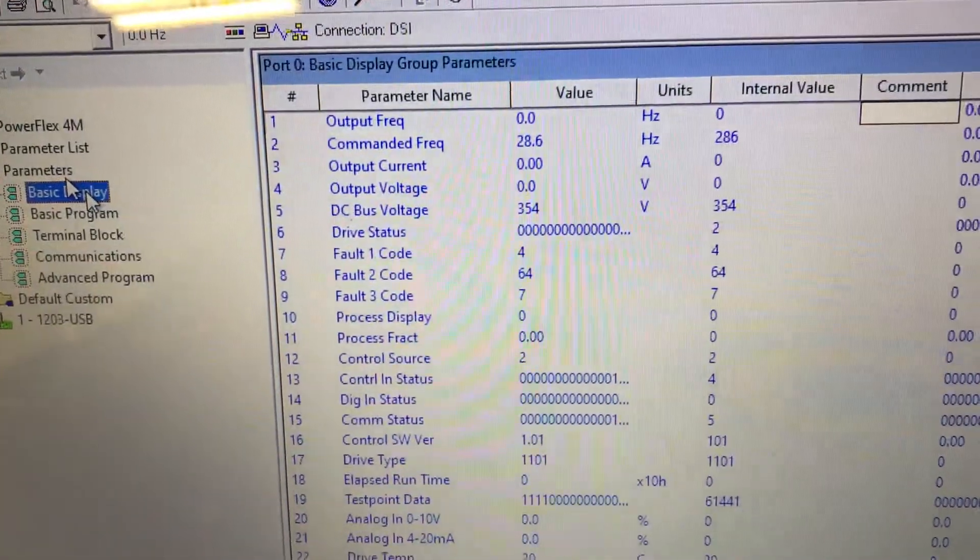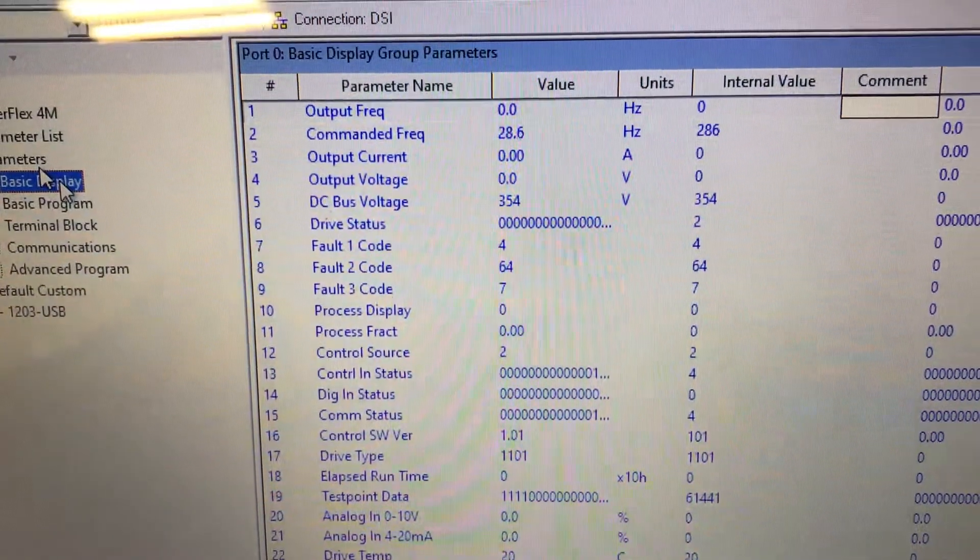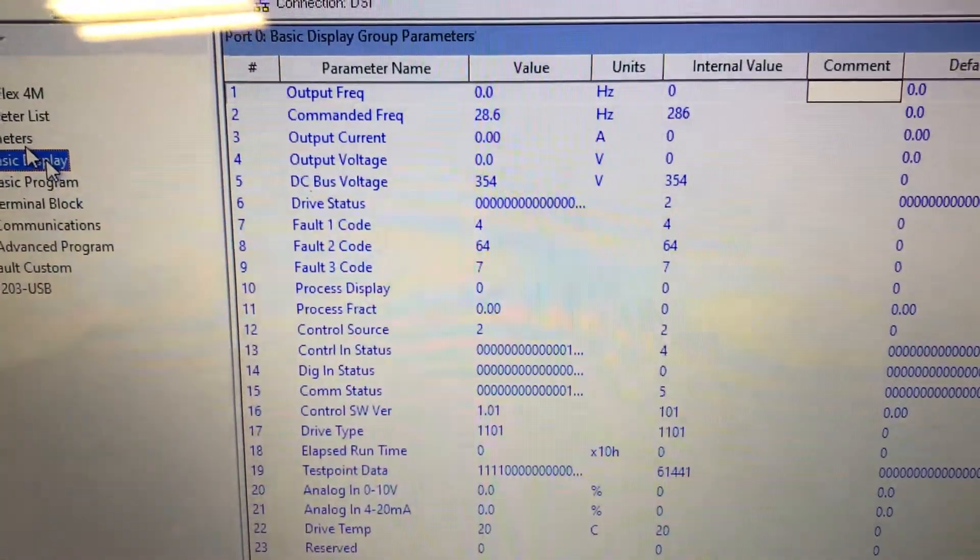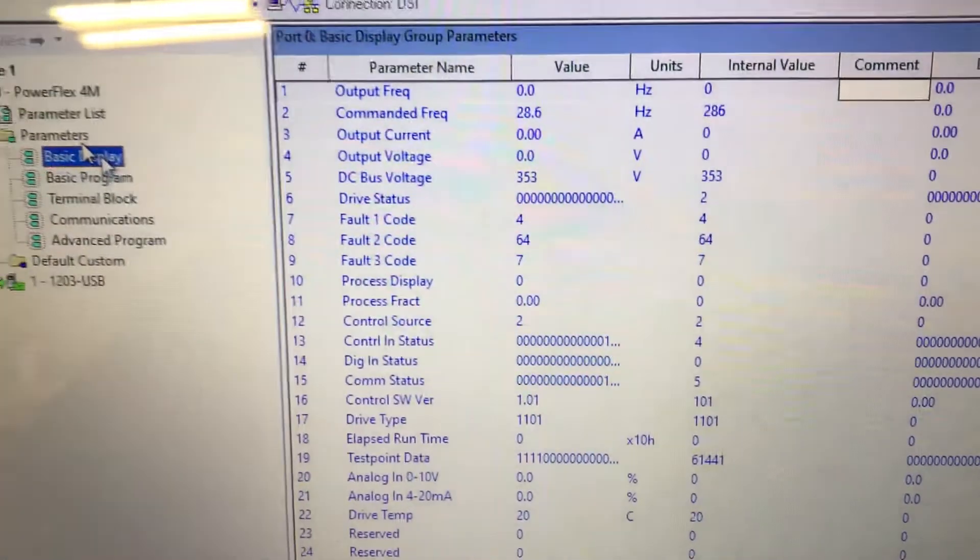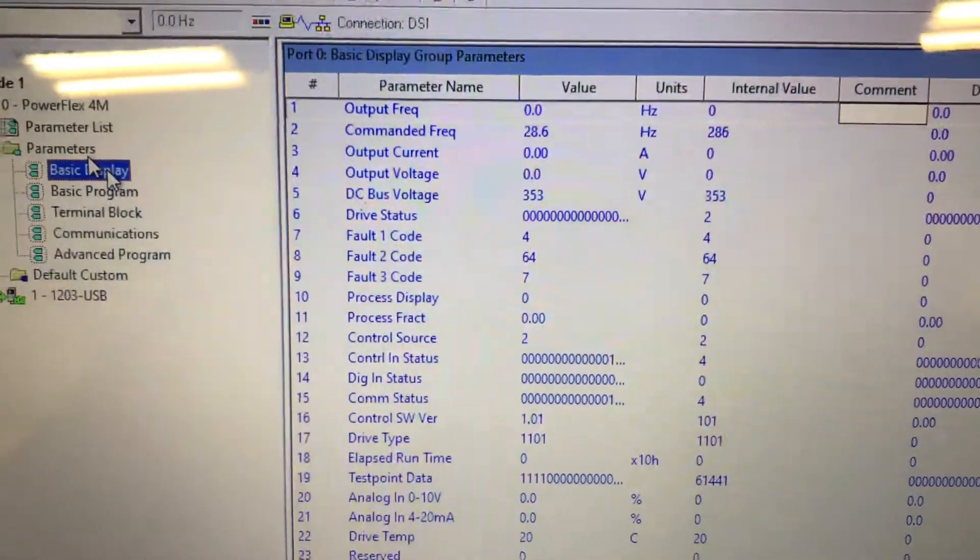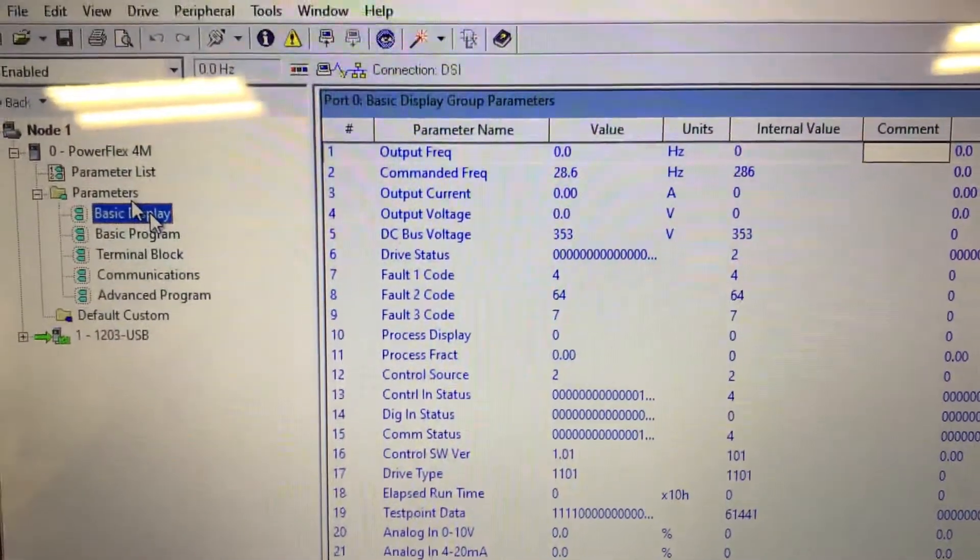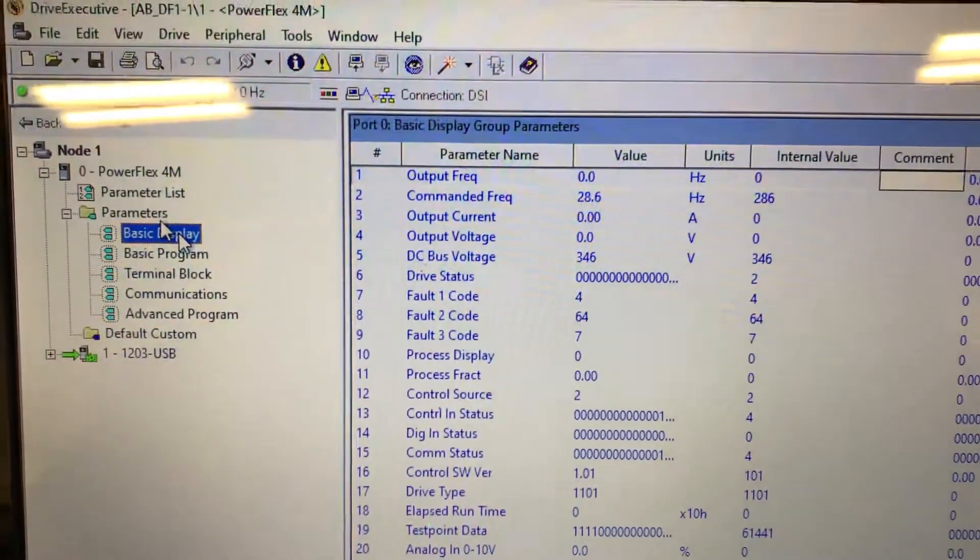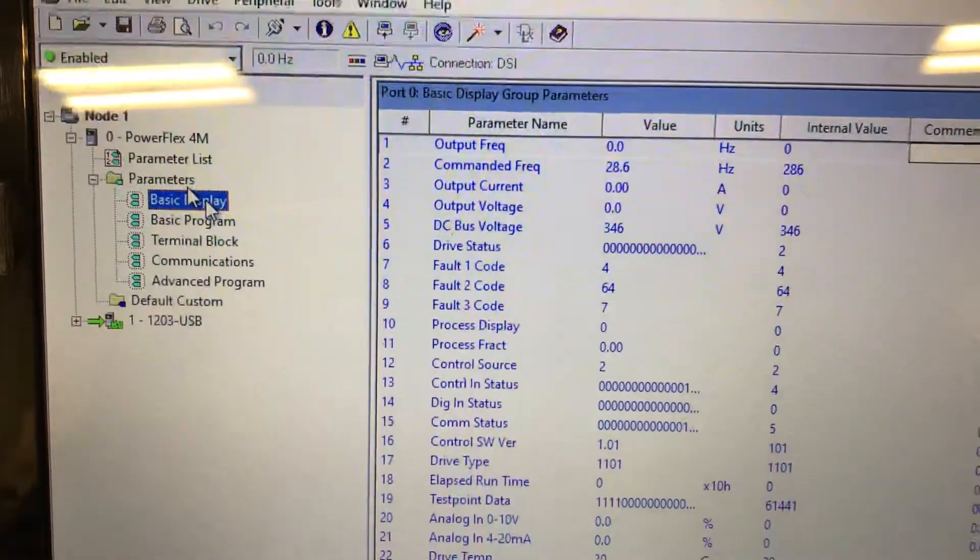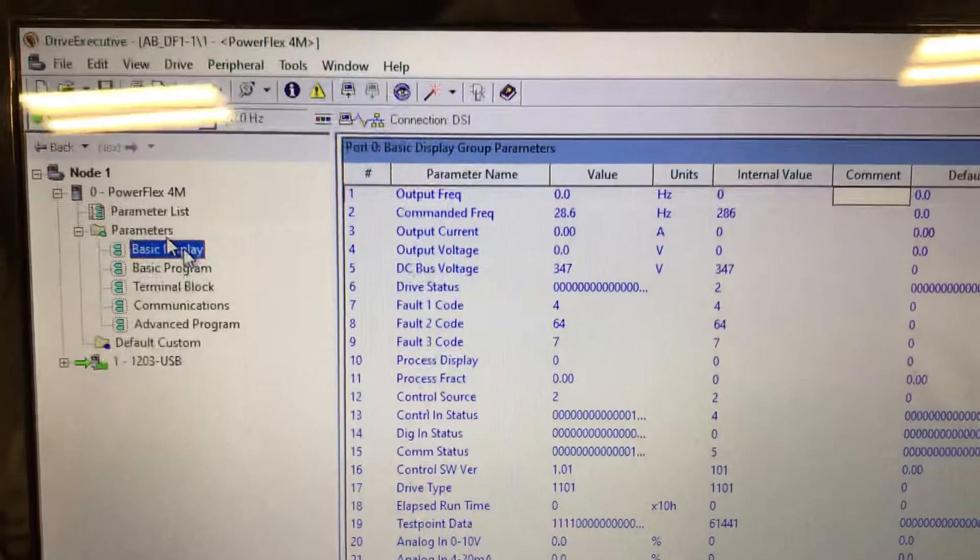Our software is now telling us we're still commanded 28 Hertz, but our output frequency is zero, no current, and no output voltage. But our DC bus is still at 354. During our course, we go through why that would have a DC bus voltage and at what level it should be.